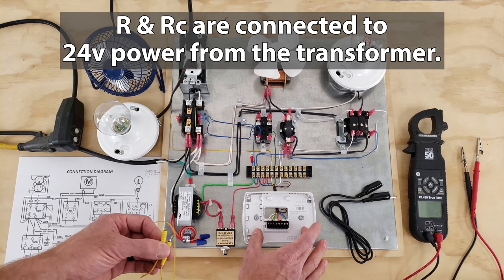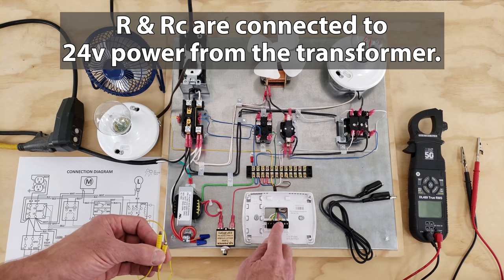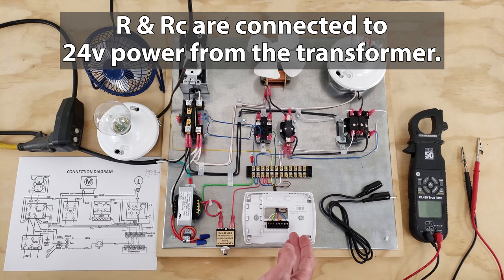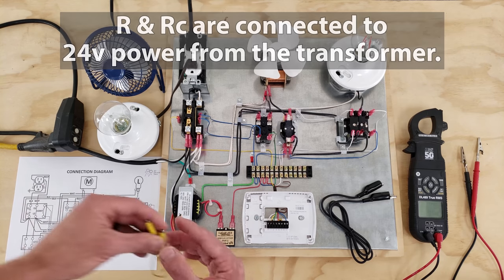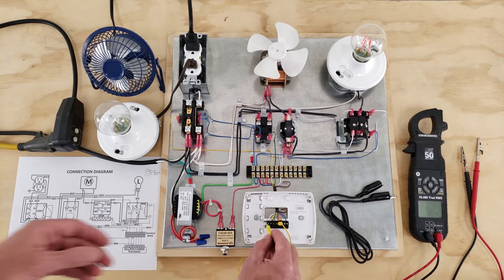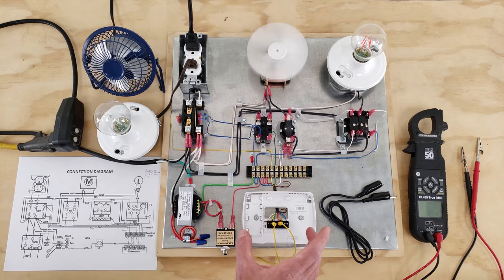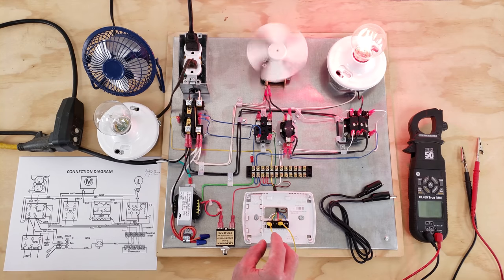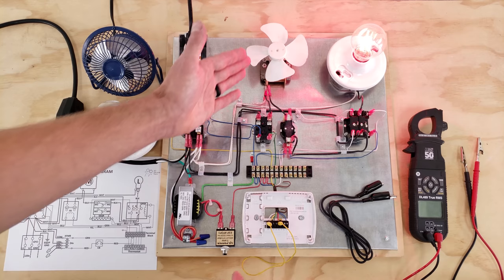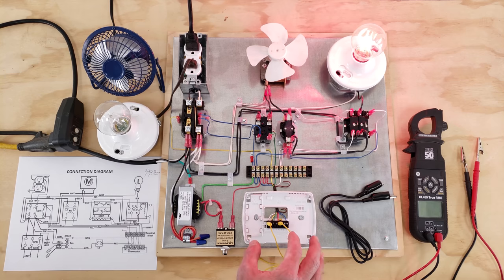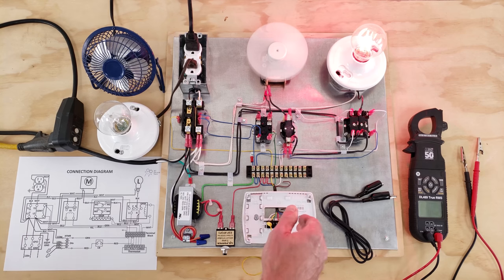Now this is an older thermostat, and you see that we have our RC and R has a jumper inside the thermostat. Some may have just a dip switch or a program inside the thermostat, but in this case it's just a little jumper. And so we can jump from R to G, and so that just acts as a switch. That's all this thermostat is. And so we can do the same thing from R to W right there. And so remember that our sequencer is not going to power the indoor fan on until, say, our heat exchanger heats up. But I just wanted to show you how you could use these magnet jumpers to be able to teach how a thermostat works. So you can remove this.